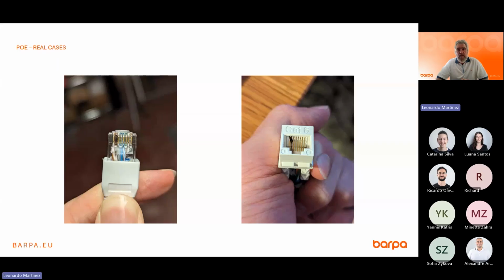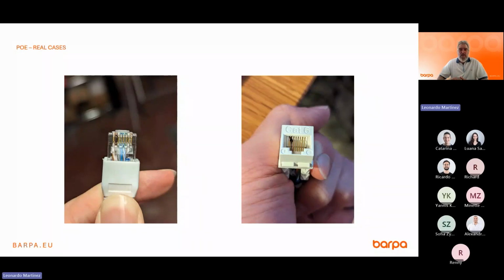An important point to take into account when you use PoE is that all components have to be PoE ready. For cables, it's very easy because the cables should have good resistance performance, and resistance imbalance should also be tested to see if there is a difference between resistance between pairs, and also between the two wires of each pair.